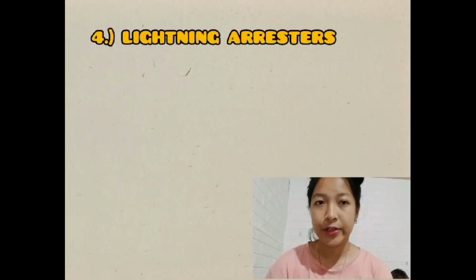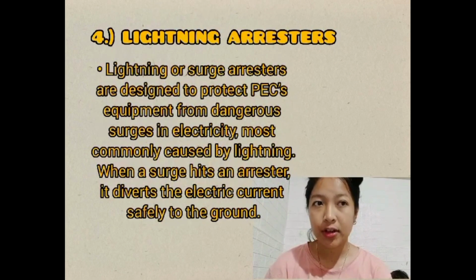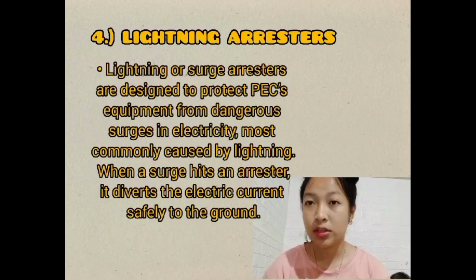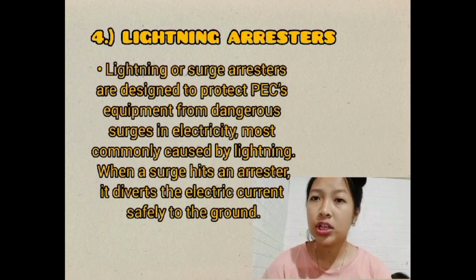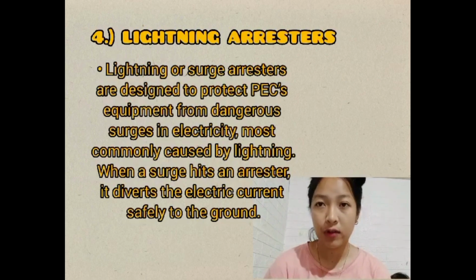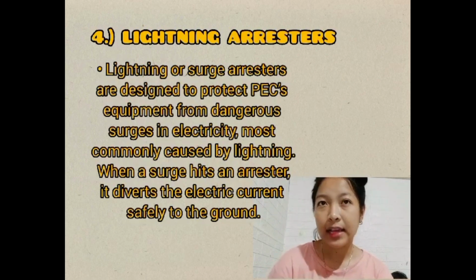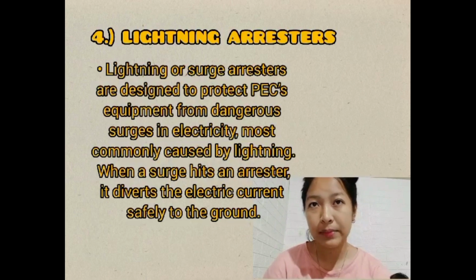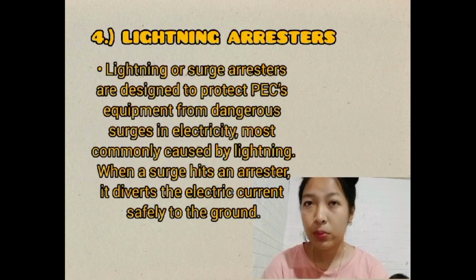Lightning arresters. Lightning or surge arresters are designed to protect PECS equipment from dangerous surges in electricity, most commonly caused by lightning. When a surge hits an arrester, it diverts the electric current safely to the ground. The arrester acts as a conductor, allowing surge energy to flow to ground. That keeps the substation equipment within design limits and protects the equipment from damage. When voltage returns to normal, the arrester stops conducting.